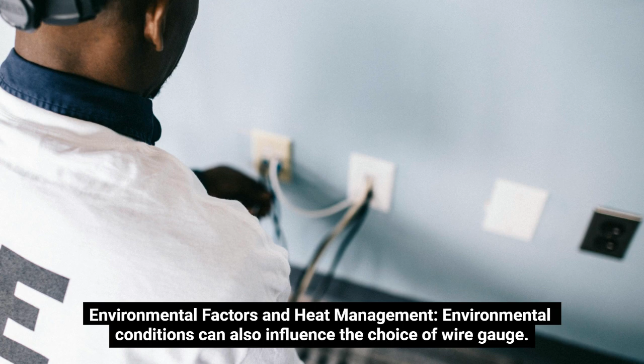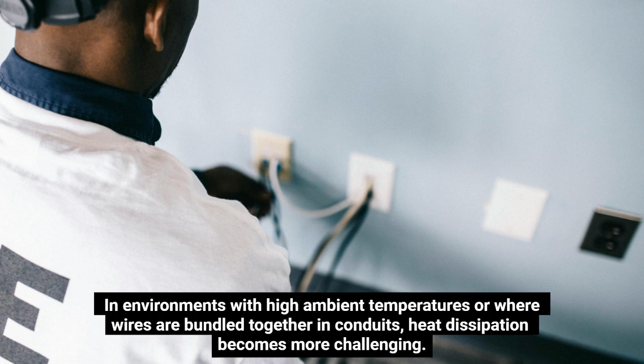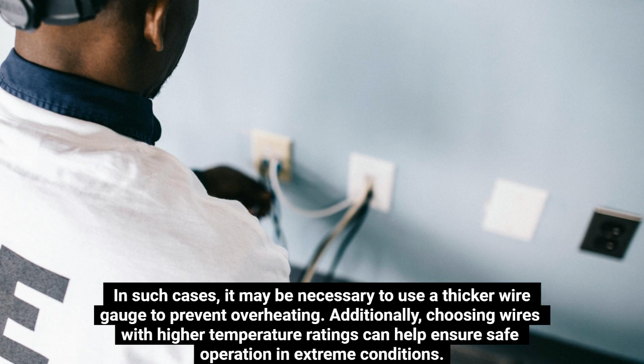Environmental factors and heat management. Environmental conditions can also influence the choice of wire gauge. In environments with high ambient temperatures or where wires are bundled together in conduits, heat dissipation becomes more challenging. In such cases, it may be necessary to use a thicker wire gauge to prevent overheating. Additionally, choosing wires with higher temperature ratings can help ensure safe operation in extreme conditions.